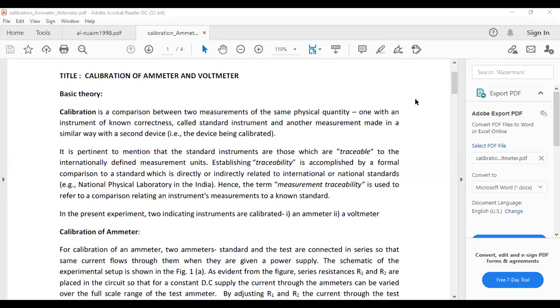So calibration of ammeter and calibration of voltmeter. Calibration means basically the comparison between two instruments. Now, when we are going for ammeter calibration, we'll take two ammeters. One will be standard, another will be test. With respect to the standard ammeter, we'll check whether there is any error, and if there is any error, then we will map it for all the readings.